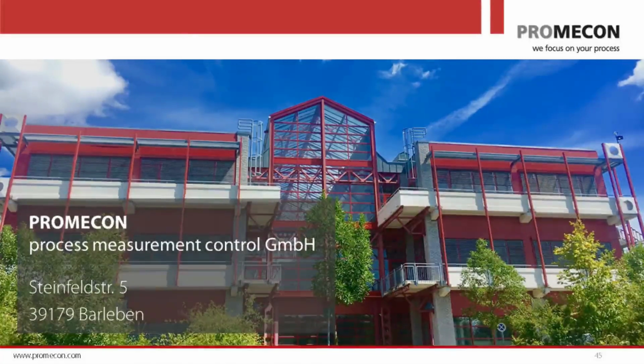So if you send us a drawing from these, we can get you a very good installation position, and that usually includes drilling a hole, putting a mounting adapter on, and sticking our sensors into that location. And you could even run the existing venturi or the existing aerofoil parallel. So if you want to do a test, you don't even have to put our sensor into your DCS before you have tested it. You can just put it in parallel, and then you can see how both run parallel. But finally, for the final installation, you can then hook it all up to your DCS, and you will have a very good measurement. So the question is, usually there is no big modification necessary in your boiler.